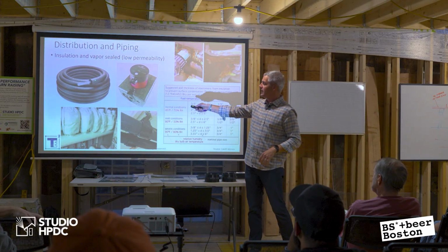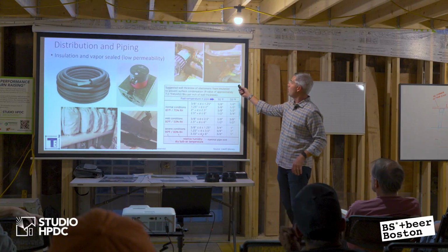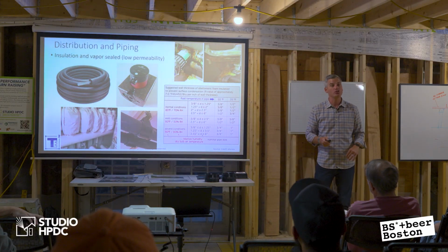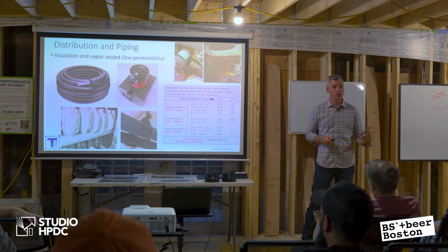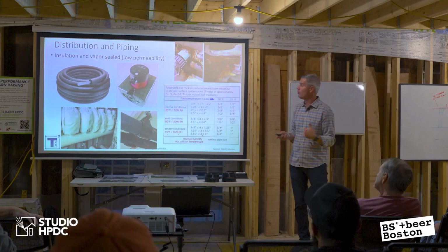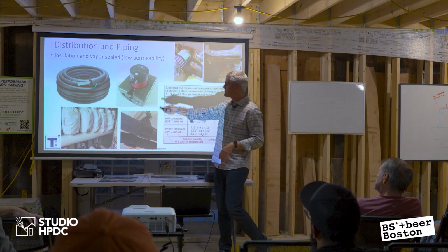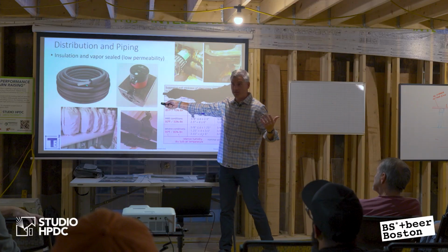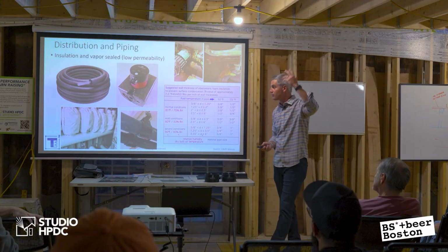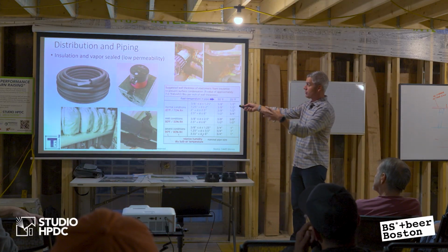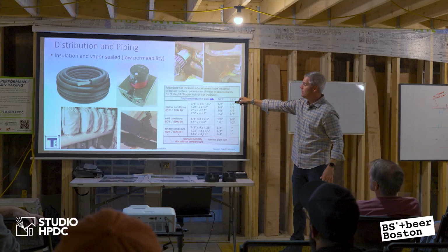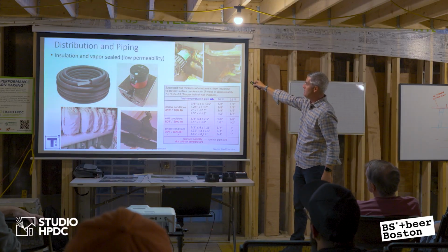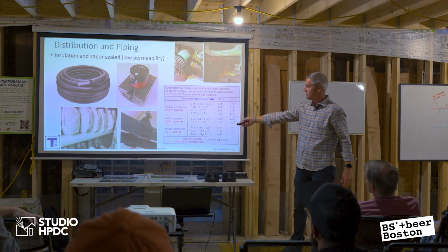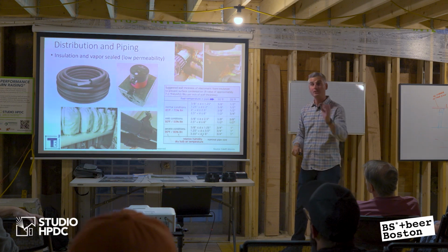One is that the piping has to be insulated, because it will condense, it will sweat. Chilled water could be at 45 degrees, could be below dew point. So you have to have valve wrap kits, or PEX that's pre-insulated. They sell rolls of it, and you can snake it through. They have these things called clamshells that wrap around the pump so that this doesn't happen. And they have insulation that can be continuous throughout. So that is one big caveat.